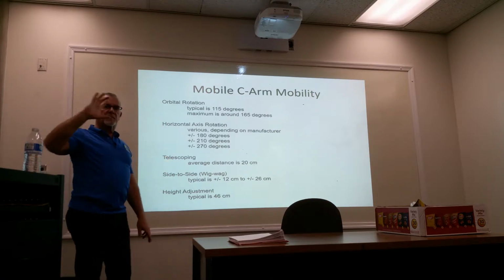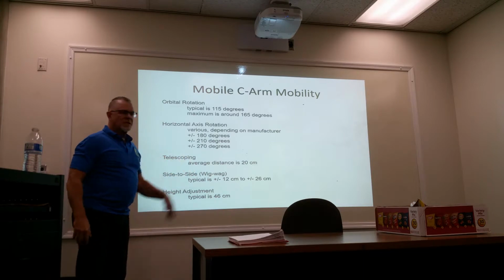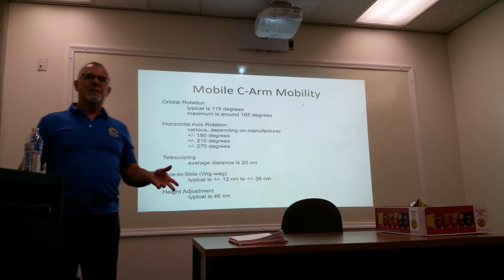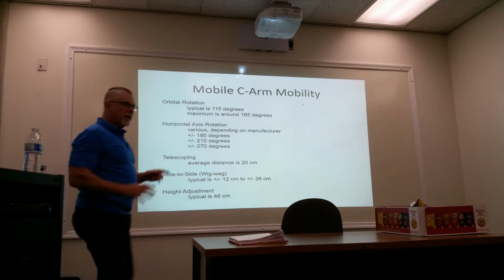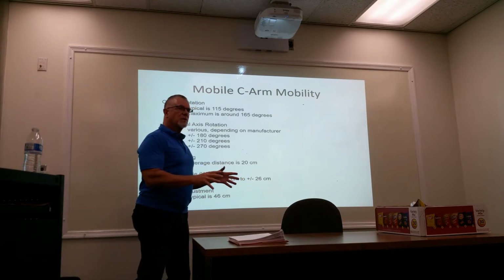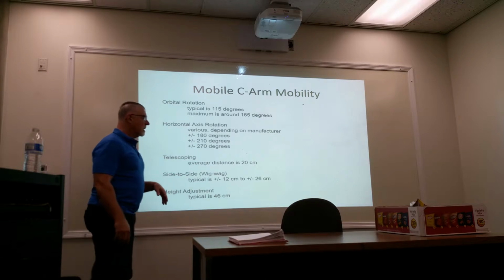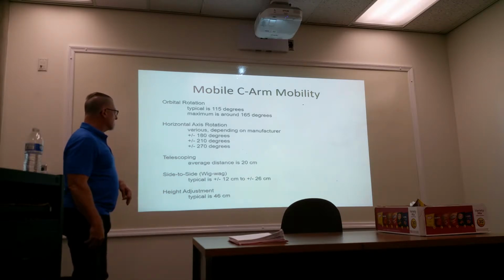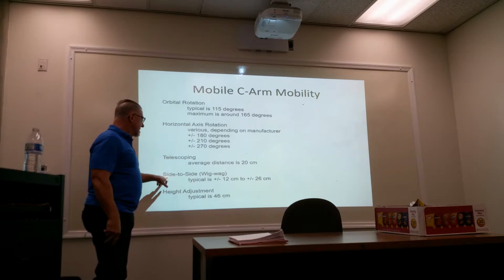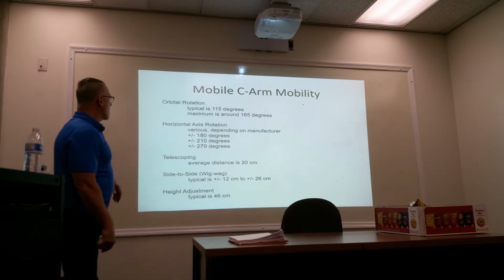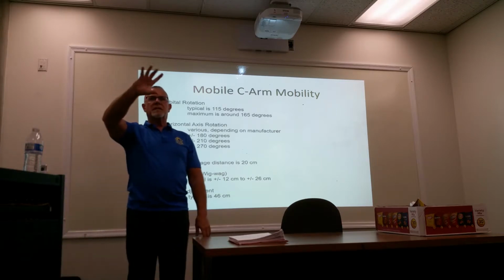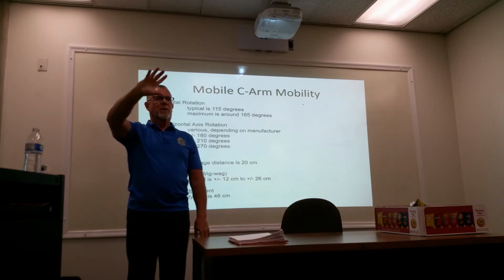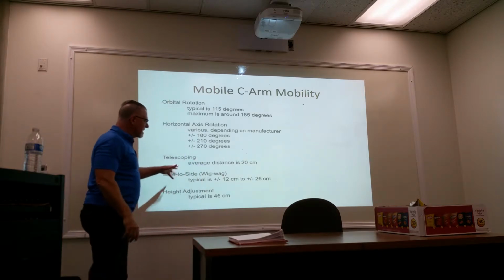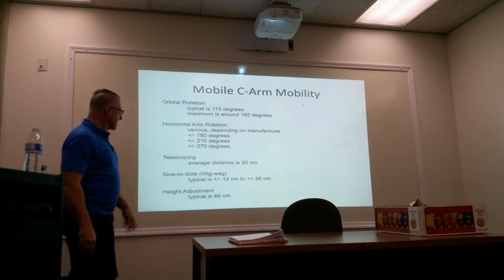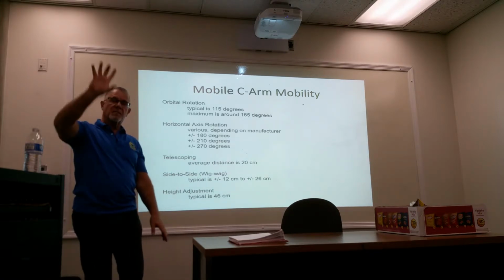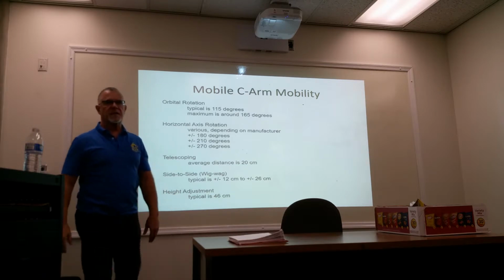Telescoping is where the entire C moves in and out. Usually, average distance is about 20 centimeters. So it's not a lot, but that allows you to get close, but you don't have to get right up next to where you need to be. You have a little bit of movement there. Side to side is what we call wig-wag. That's where the C does this. It's not much, plus or minus 12, plus or minus 26. Then your height adjustment, where the whole C goes up and down, is typically about 46 centimeters.